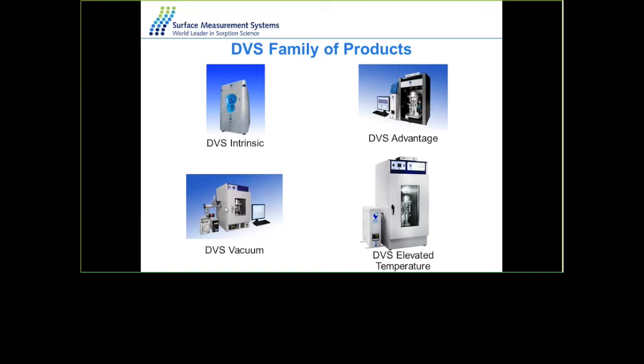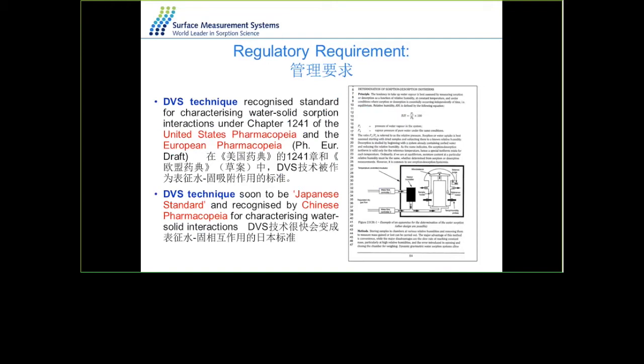The DVS Vacuum, instead of using a flow of gas, works with a vacuum using a rotary and turbo pump, going down to vacuum levels of 10⁻⁷ Torr. This is ideal for porous materials as well as for measuring the vapor pressure of solids. In terms of regulatory requirements, the system has been recognized by US Pharmacopoeia and European Pharmacopoeia, and is becoming a standard method in Japan and China as well.